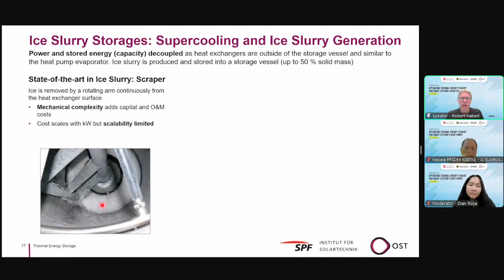But there is also another technology available to produce ice. That is the ice slurry generation. That's again with a heat pump. You have a heat pump and you extract heat on that supercooler, and you extract heat from water of 0 degrees, and you supercool it down to -2 degrees. If you do it with pure water, you can do it without building ice, but you already use the energy of fusion by supercooling it. And then you need a crystallizer that starts the crystallization of the water to ice, and you can store the water ice mixture then in a simple tank.